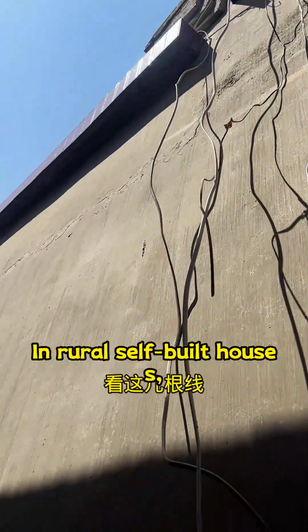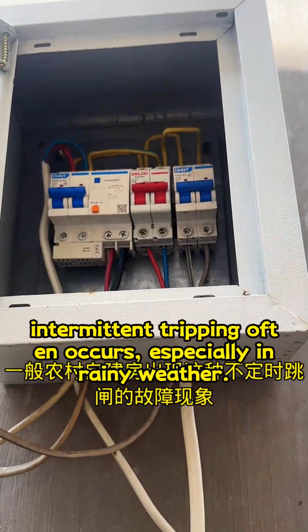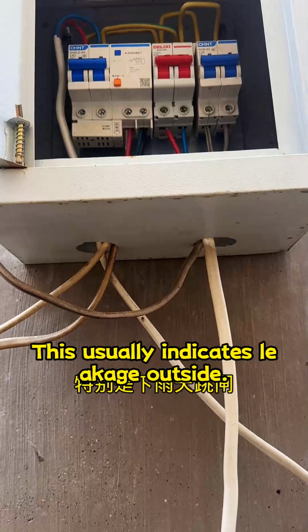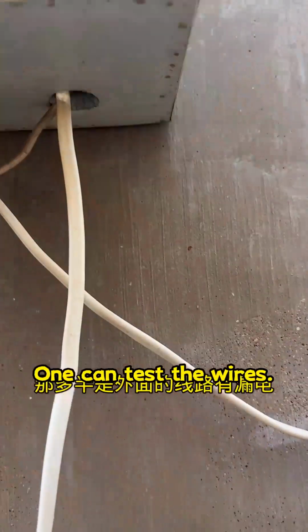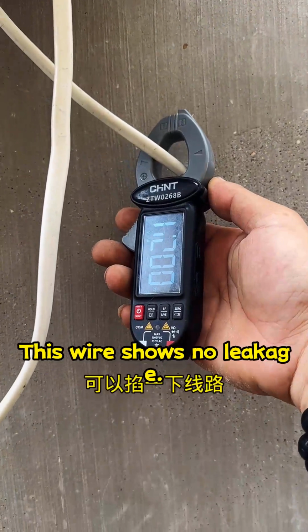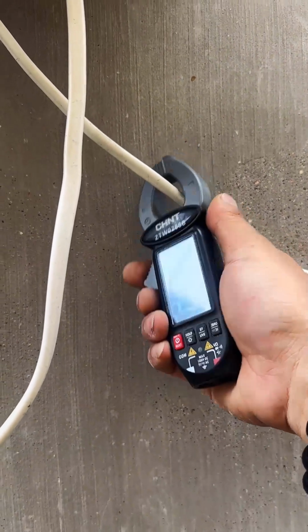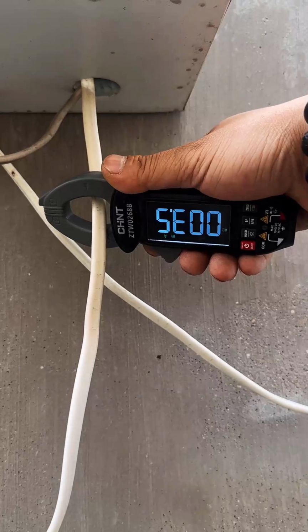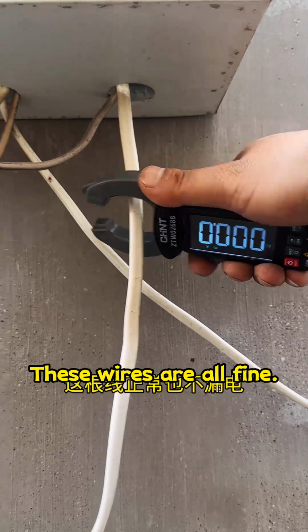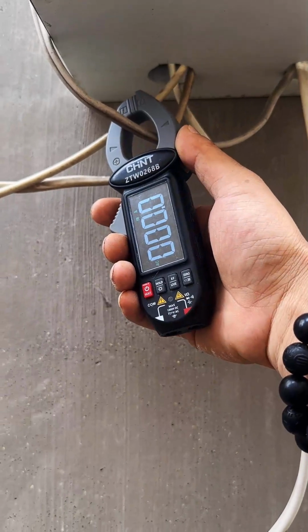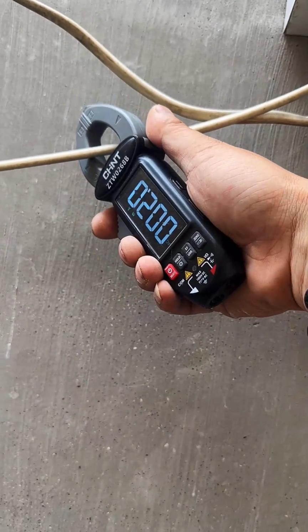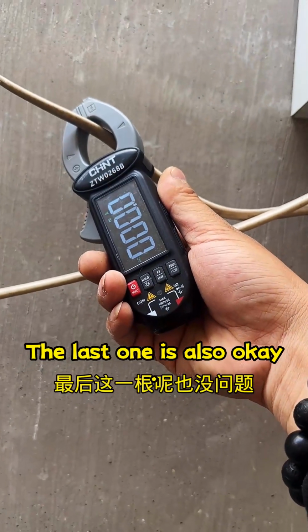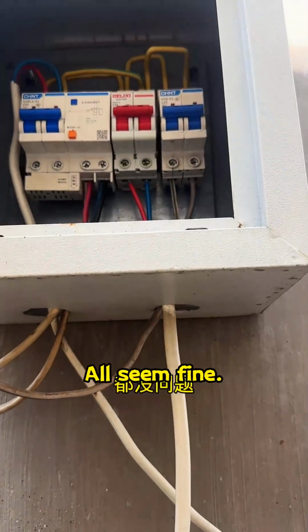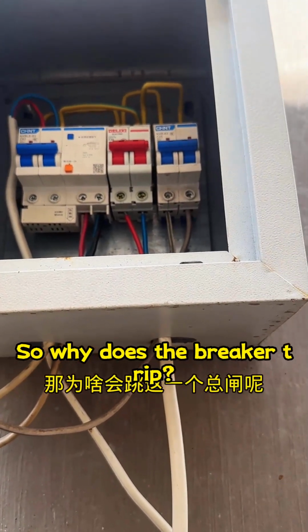In rural self-built houses, intermittent tripping often occurs, especially in rainy weather. This usually indicates leakage outside. One can test the wires. This wire shows no leakage. This wire is also normal. These wires are all fine. The last one is also okay. All seem fine. So why does the breaker trip?